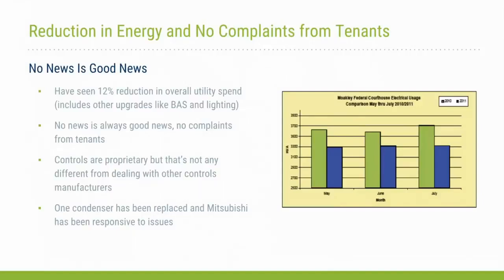But when we say no news is good news, we mean both from the building operators, being the GSA property management staff and our O&M contractor there, but also the tenants have no complaints as well, so that is always a good thing. It's been spoken to, and I see some of the questions in chat. Yes, we did find that using the proprietary controls that come packaged with the unit was actually very good for the install. But we do have supervisory of that linked into our BAS. So there is a question about, do you have package controls on your chiller system that are packaged to the chiller system, but then talk back to your BAS, and your BAS monitors that system. And that is exactly what we use there at the Moakley.